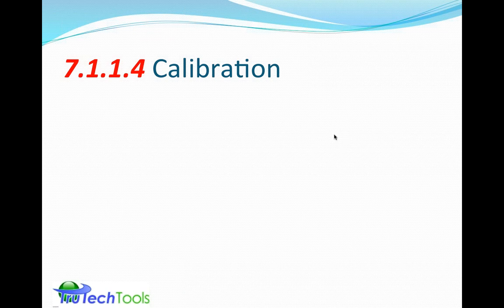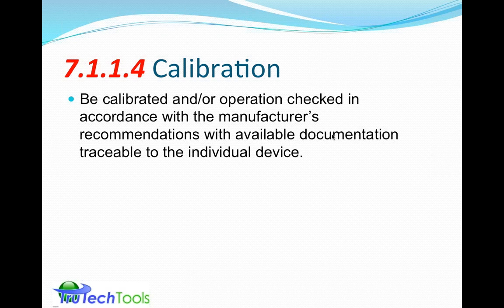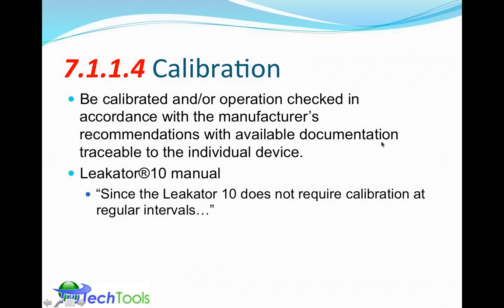Section 7.1.1.4 talks about calibration of the combustible gas detector, and the statement has been rewritten since the last revision. They're looking for it to be calibrated or checked in accordance with the manufacturer's recommendation, with any available documentation traceable to the individual device. So basically, they want calibration records of whatever sort kept, conforming with the manufacturer's recommendation. Now, there's still a little problem here because the Leakator 10 manual does say the Leakator 10 does not require calibration at regular intervals. So there's a little bit of meshing that will have to be done here between the manufacturers and the standard. I expect a few more explanations or corrections as we go forward with this.